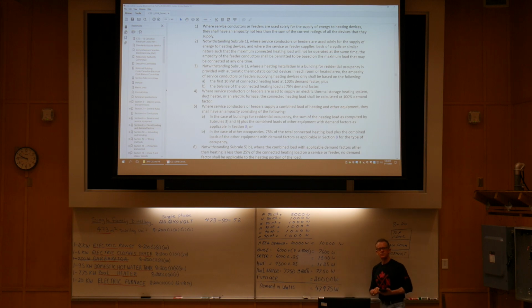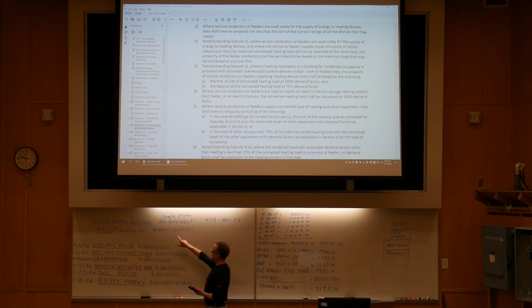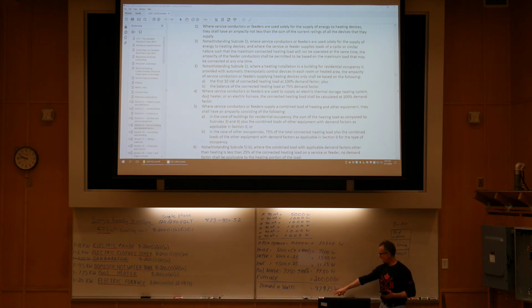All right, so that is 8-200 subrule 1(a), which is perform the calculation. You perform the calculation, we add it up, and the demand for the service in watts is 47,975 watts.